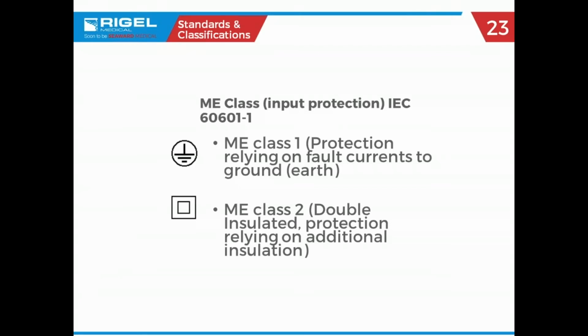Now there's a lot of manufacturers that still test class 2, and they even go as far as taking the ground probe or the test probe, taking a piece of copper foil or aluminum foil and wiping the chassis, looking to see if they get any current reading on the safety analyzer.